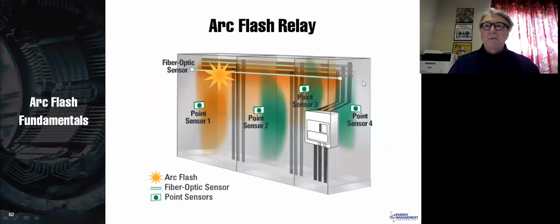This is fairly common. This is another method that you can use, and that is an arc flash relay. Instead of looking at the current, you can look at light. And so you can look at light and you can have a time delay, but have an instantaneous trip in case there is an arc flash by using the fiber optics in there to sense the actual appearance of light. Now remember that that's going to sense the appearance of light here, and it may help you in these points that are fed by the main breaker.